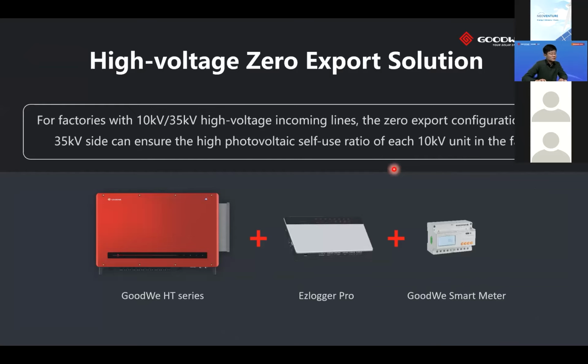Everybody knows that C&I projects normally connect to the high voltage power grid. We design our products to achieve zero export, and even support high voltage grids for both 10 kilovolt and 35 kilovolt. We support both in a very easy way, with just two more tools, Ezlogger Pro by GoodWe and GoodWe Smart Meter. With these tools combined together, we can achieve this zero export function.